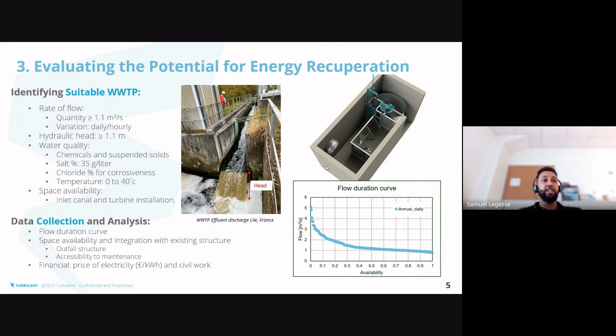This is the design value, but that doesn't mean that whenever the flow is less than 1.1 meter cube per second the turbine will stop generating. It will still generate, just not the design power. For example, if the turbine is rated 8 or 10 kilowatt for a particular flow, whenever the flow is less than 1.1, it might generate 5, 6, or 7 kilowatt instead. We'll analyze this during the feasibility stage of the project, but keep in mind that at this moment we need a minimum of 1.1 meter cube per second to install a turbine in a wastewater treatment plant.